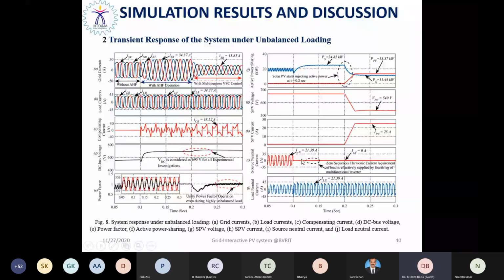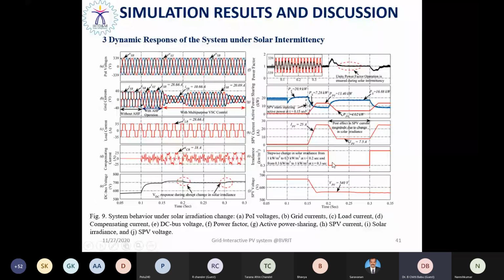This is the dynamic response during solar intermittency. Due to changes in the irradiation, the grid current also changes, but throughout the case the dynamic response is excellent because the DC link voltage follows the reference trajectory of 690 volts. It provides an excellent dynamic response and contributes to DC link voltage stabilization, so the overall performance has been enhanced. The grid current waveform is in phase with the voltage, and again it operates at unity power factor. And this is the experimental result with the active harmonic filter operation.